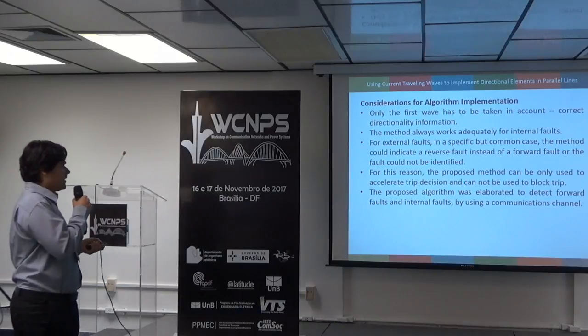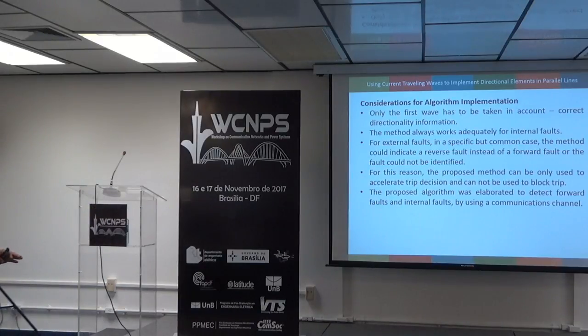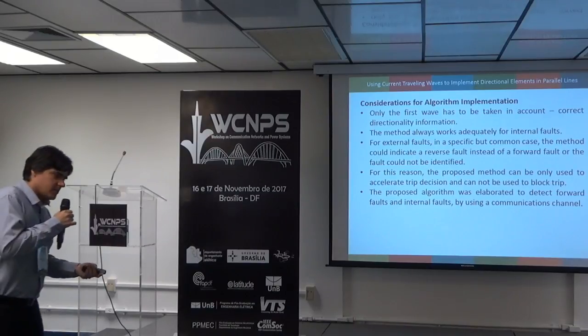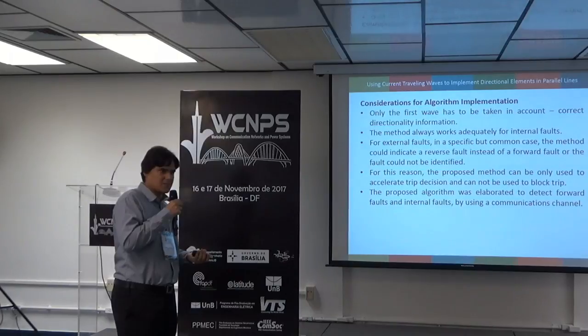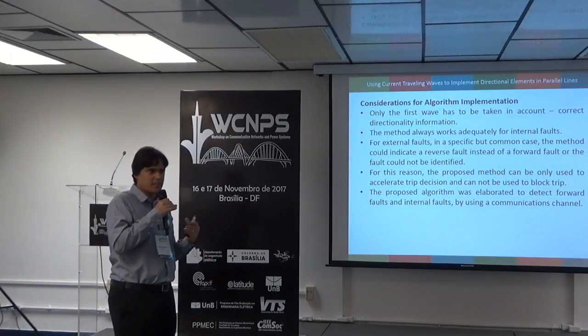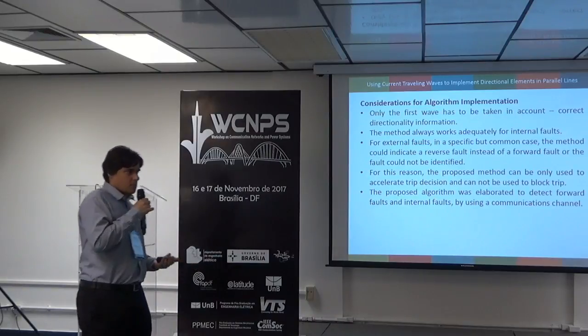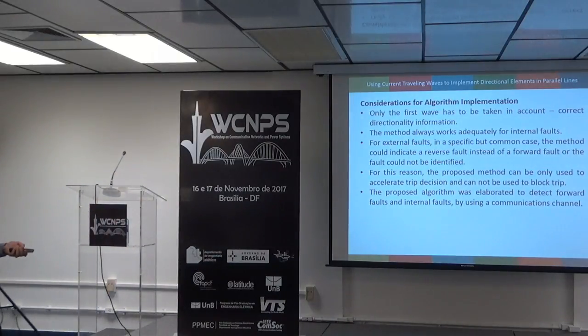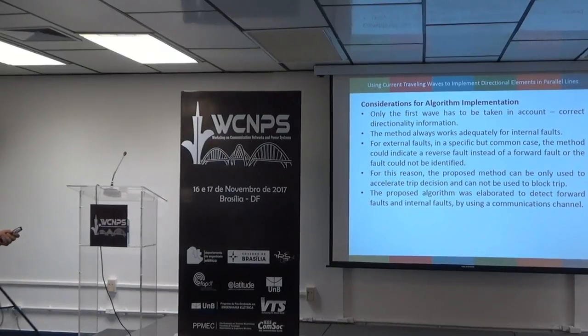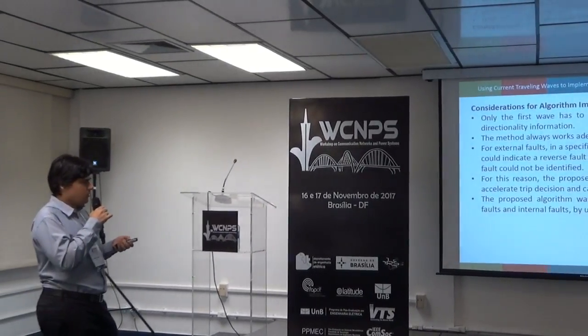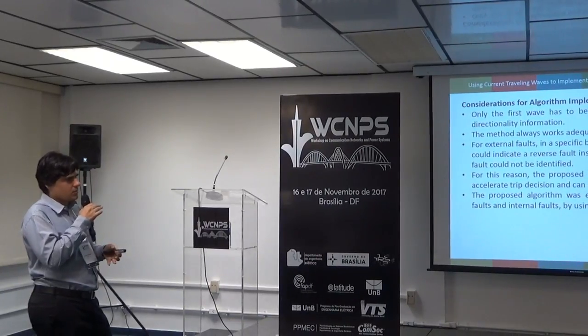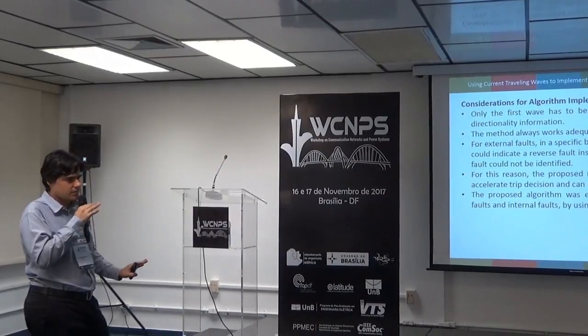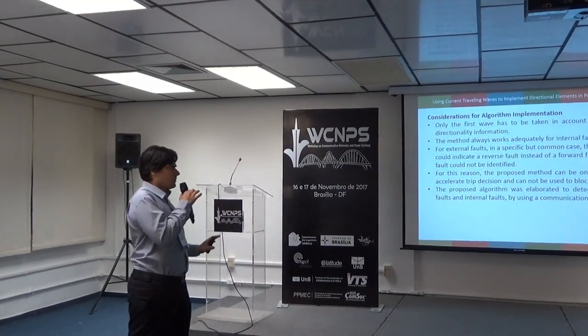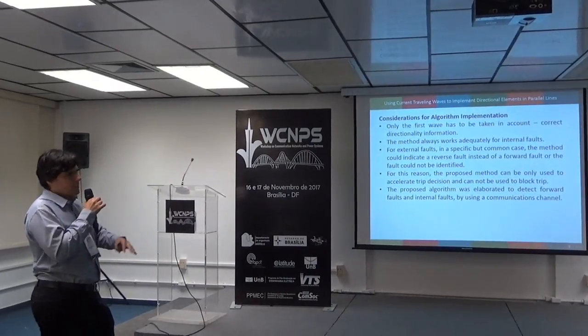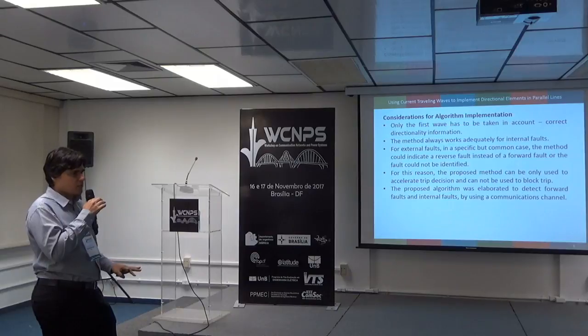Because of that, the proposed method can only be used to accelerate trip decision and cannot be used to block trip. In other words, if the method indicates a forward fault, it is a forward fault. But if it indicates a reverse, it could be a forward. But if you use the method to accelerate, it's an advantage, because it always works. And because of that, the algorithm implementation only detects if the forward fault occurs, or not detecting a forward fault. And if you detect a forward fault in both terminals, it is an internal fault with certainty.